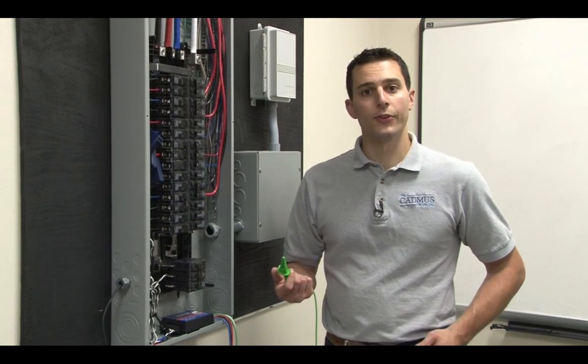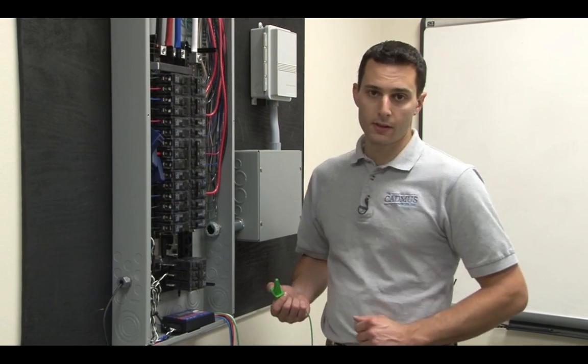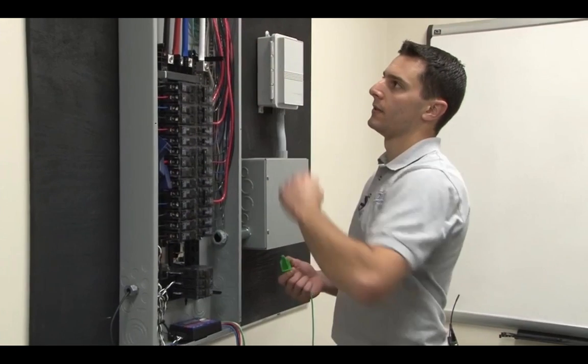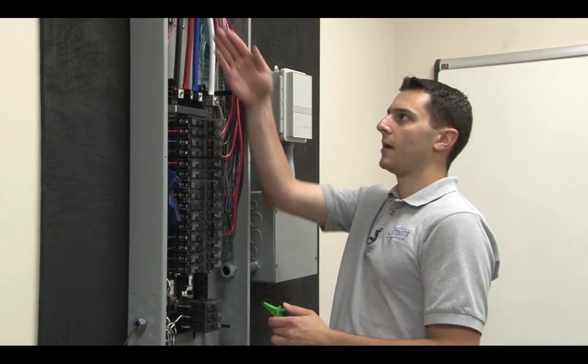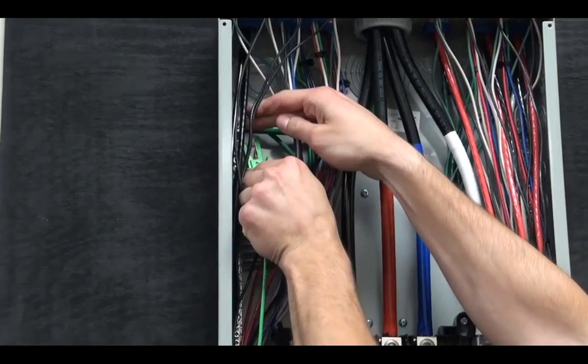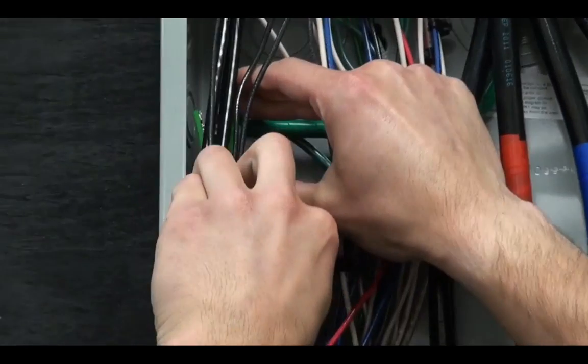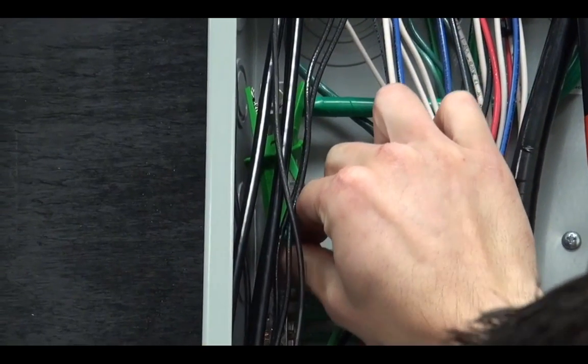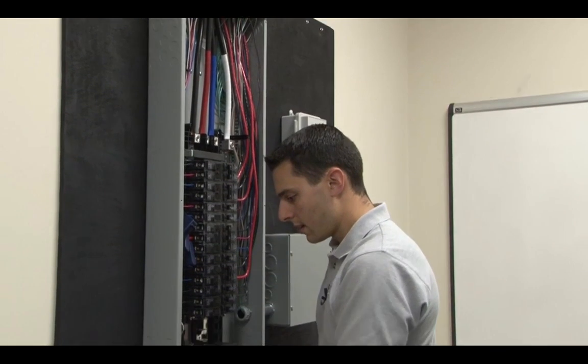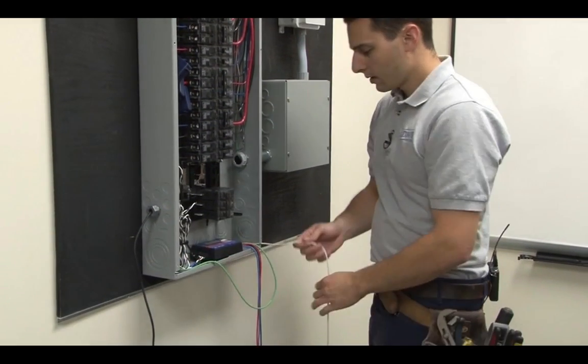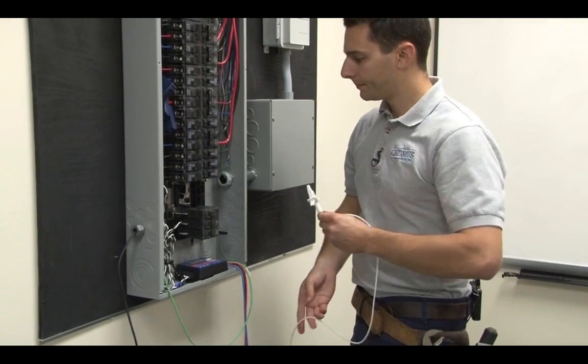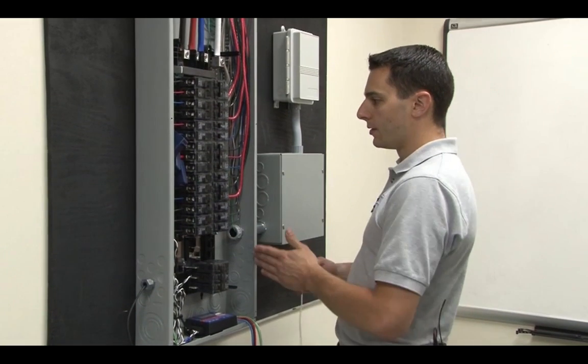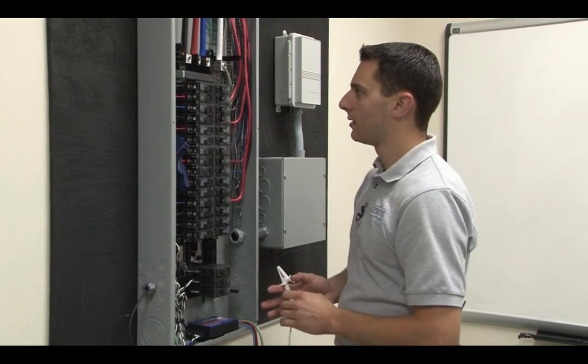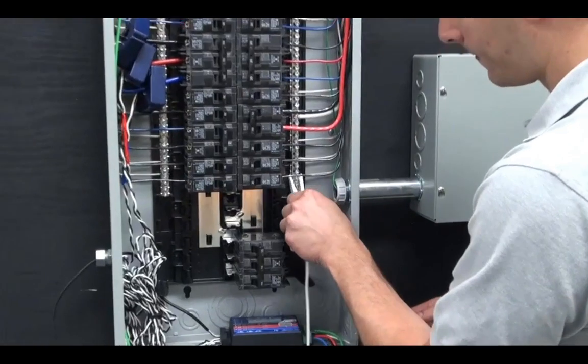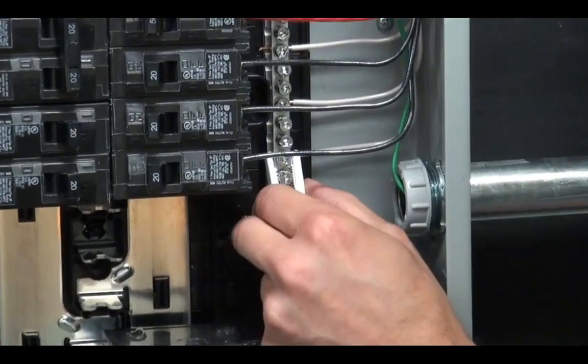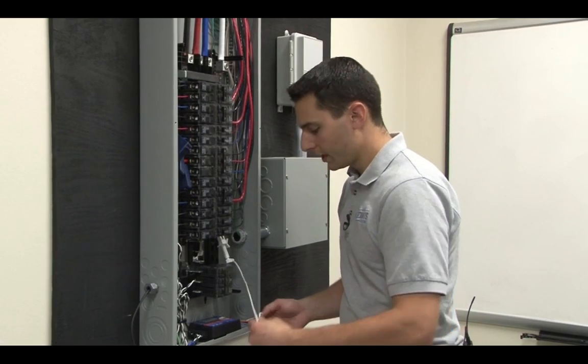We'll start with the green ground voltage lead. This can be connected to any part of the metal in the enclosure or one of the two ground bus bars in this panel. For this, we'll connect it up in this corner. We want to make sure it's nice and secure, and we'll run the cable safely along, out of the way of the other cables. The next connection will be the white neutral voltage lead. In this particular panel, the neutral bus bar is on this side and this side, and for convenience we'll go right over here. Again, we'll make sure we have a good secure connection, and we'll neaten up our lead.